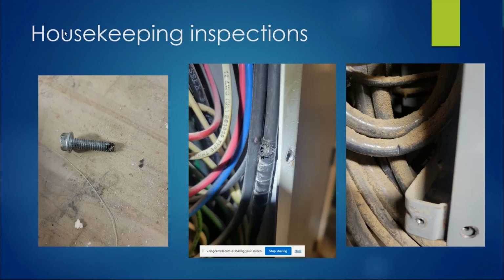So in this case, you can see where the screw on the left was run through the panel board and hit the wire. This is a big problem with panel boards that have covers with this style of bolt coming in. We don't like to see self-drilling and self-tapping screws for this reason. They're notorious for cutting into wires on the back side of the panel. So if you're replacing your hardware on these panels, use a shallow bolt if possible. Do not use self-drilling, self-tapping hardware, as they will cut into wires and shield the wiring on the back side.